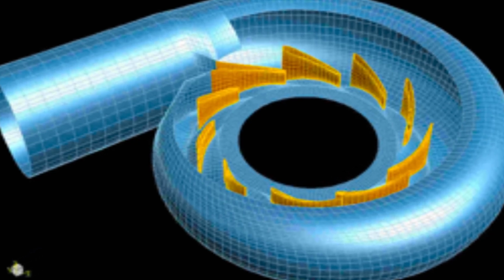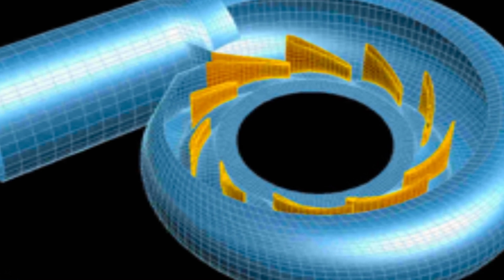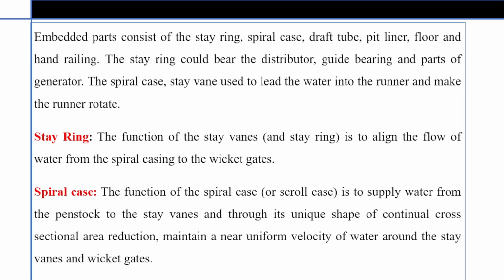Spiral case. The function of the spiral case or scroll case is to supply water from the penstock to the stay vanes and, through its unique shape of continual cross-sectional area reduction, maintain a near uniform velocity of water around the stay vanes and wicket gates.